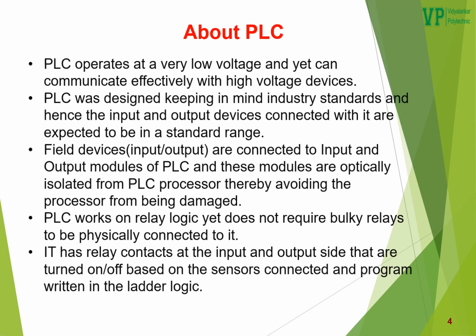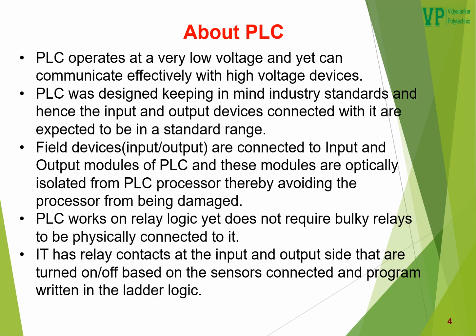Now, something about the PLC that we need to know. A PLC operates at a very low voltage and yet it can communicate effectively with high voltage devices. PLC was basically designed keeping in mind industry standards, and hence the input and output devices connected with it are expected to be in a standard range. Field devices, that is nothing but input or output, are connected to the input and output modules of the PLC, and these modules are optically isolated from the PLC processor, thereby preventing the processor from being damaged.